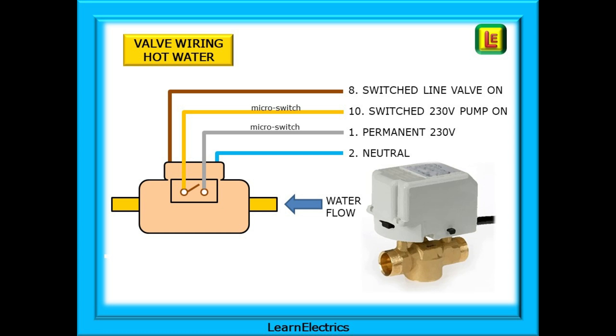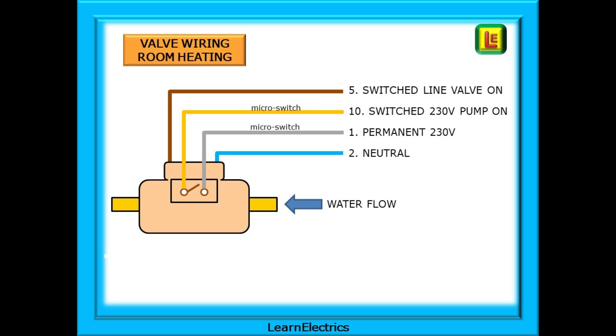You can check these against the terminal numbers that you have and confirm that the drawing matches the wiring that is in front of you because the valve wiring will not be changed. The water valve here has the brown wire connected to terminal number 8 and the valve for the room heating uses terminal number 5 for the brown wire. The other three wires use the same terminal numbers for both valves.